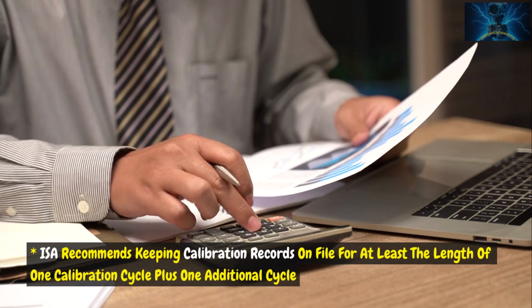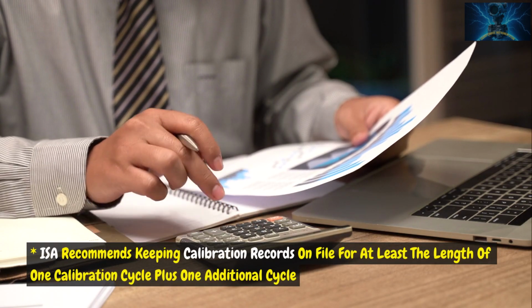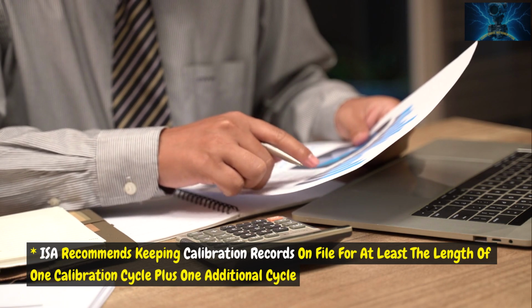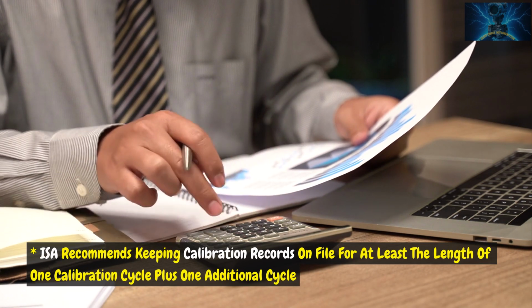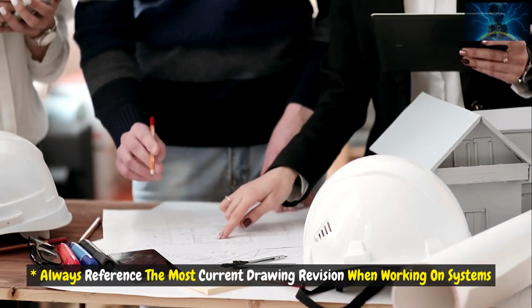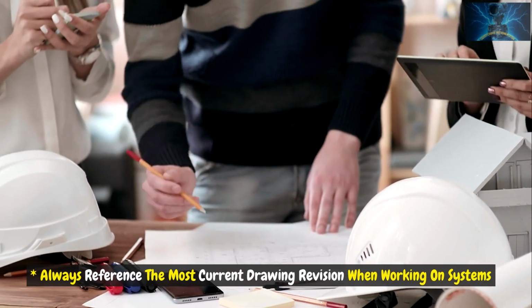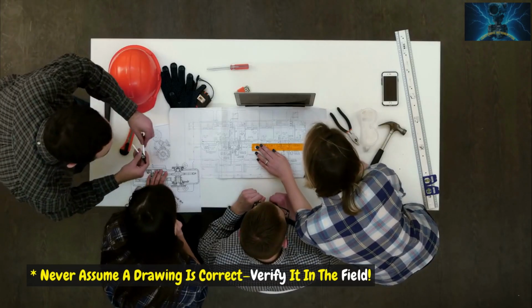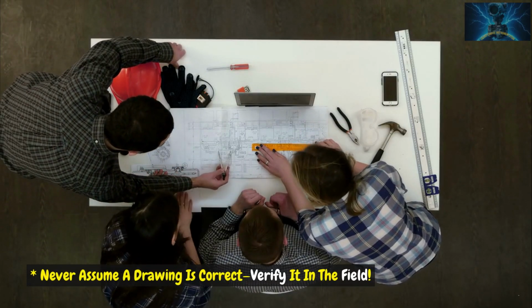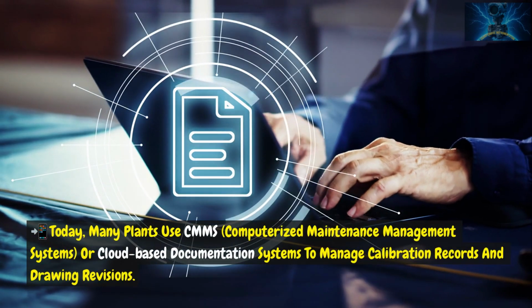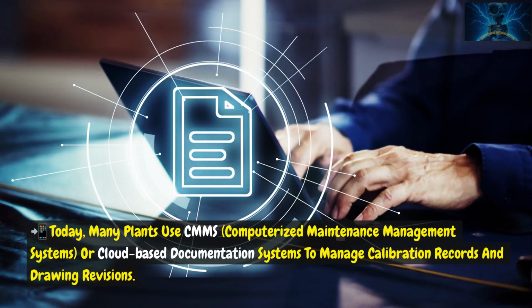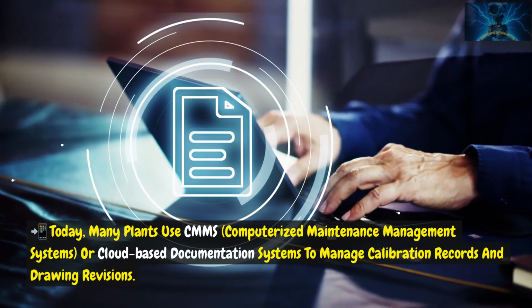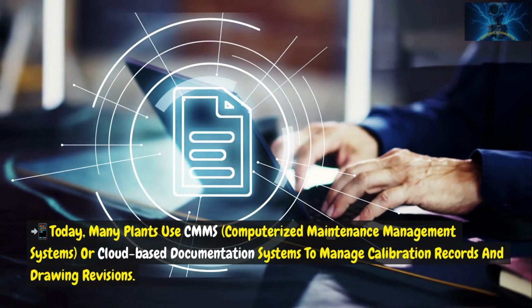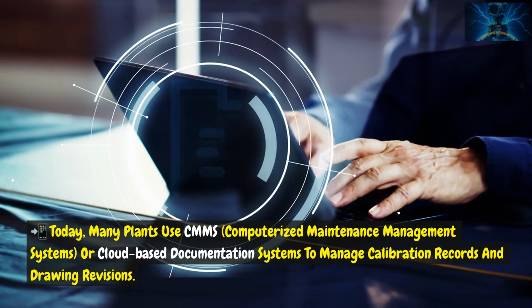Standards and best practices. ISA recommends keeping calibration records on file for at least the length of one calibration cycle plus one additional cycle. Always reference the most current drawing revision when working on systems. Never assume a drawing is correct. Verify it in the field. Today, many plants use CMMS, computerized maintenance management systems, or cloud-based documentation systems to manage calibration records and drawing revisions.